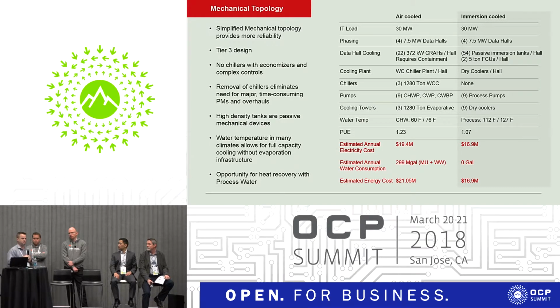One thing I did want to point out here briefly about the PUE delta, between these two and the PUE numbers we show, we actually ran a full-blown energy model on both cases here. The energy model took into account UPS losses, transformation losses. We did a lighting design. We factored in all of the key components that actually go into calculating a PUE. So I have seen in some cases before where people are reporting PUE numbers that sound almost too good to be true, and you dig into it and you find out, well, there's key bits of information missing from that. This is a complete PUE calculation with all the factors accounted for.